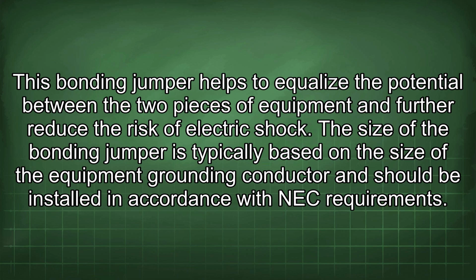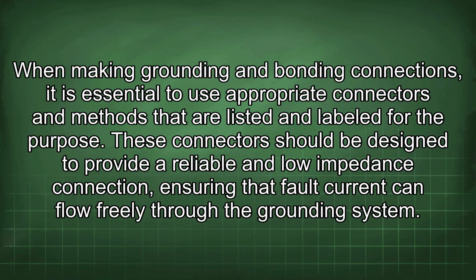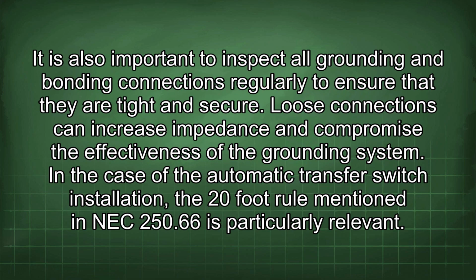The size of the bonding jumper is typically based on the size of the equipment grounding conductor and should be installed in accordance with NEC requirements. When making grounding and bonding connections, it is essential to use appropriate connectors and methods that are listed and labeled for the purpose. These connectors should be designed to provide a reliable and low impedance connection, ensuring that fault current can flow freely through the grounding system. It is also important to inspect all grounding and bonding connections regularly to ensure that they are tight and secure. Loose connections can increase impedance and compromise the effectiveness of the grounding system.